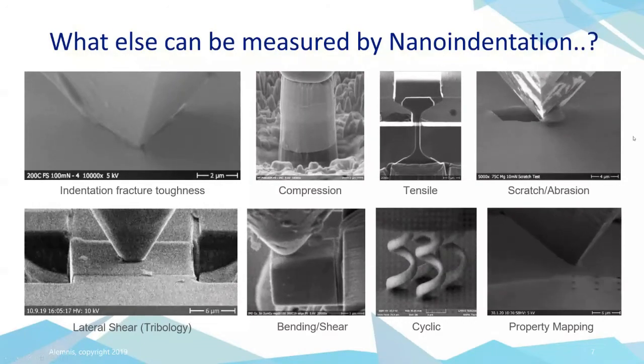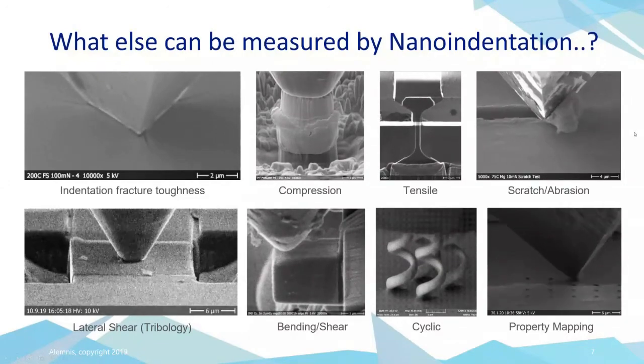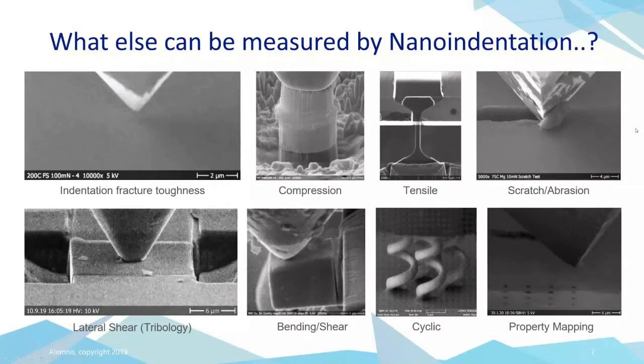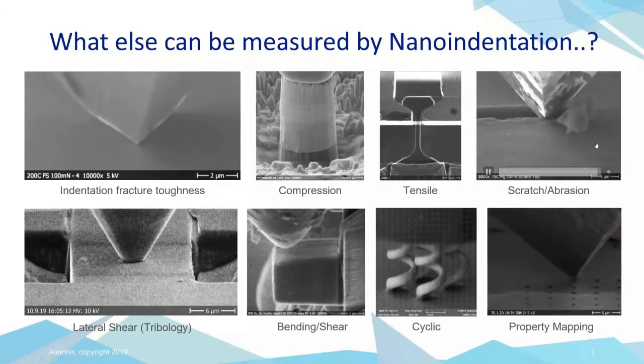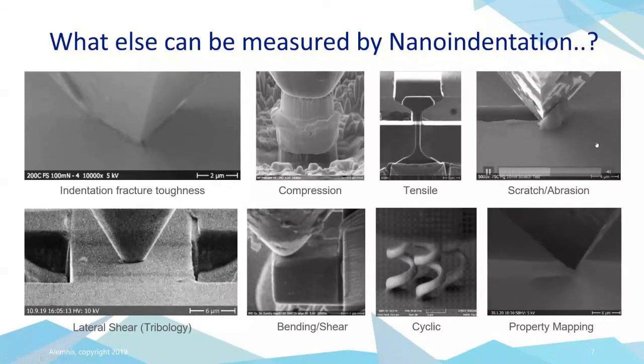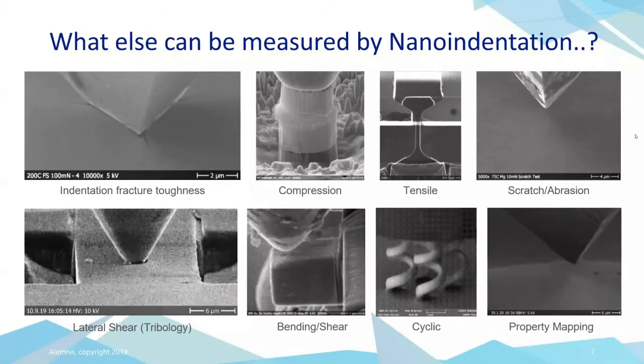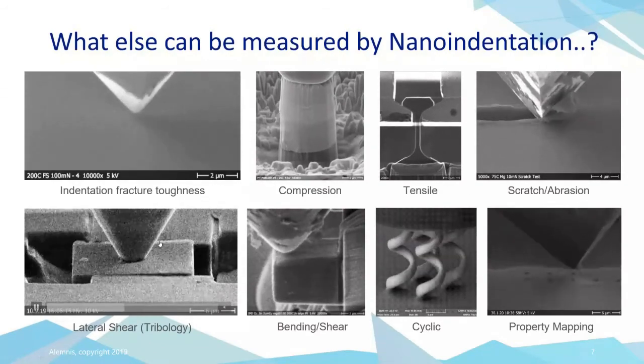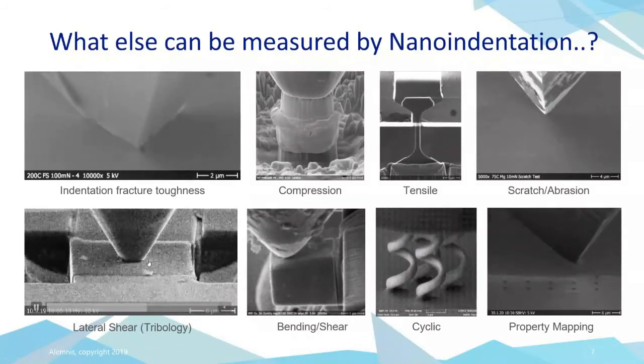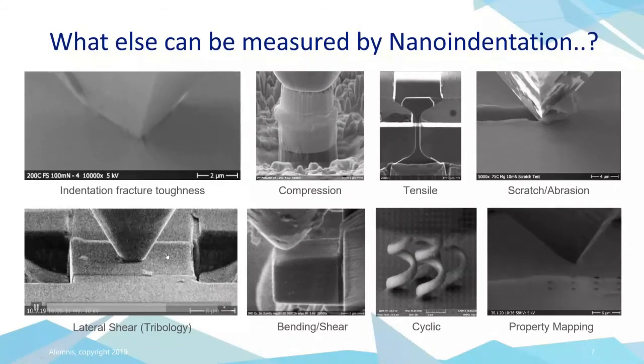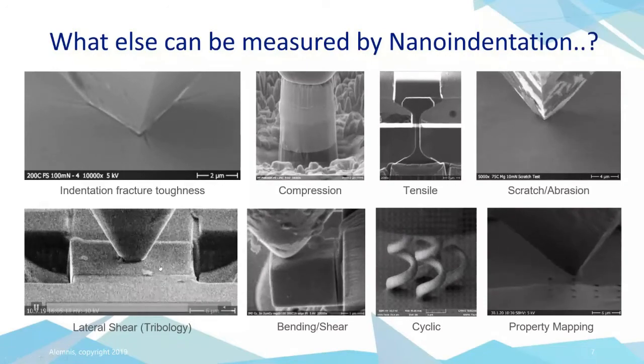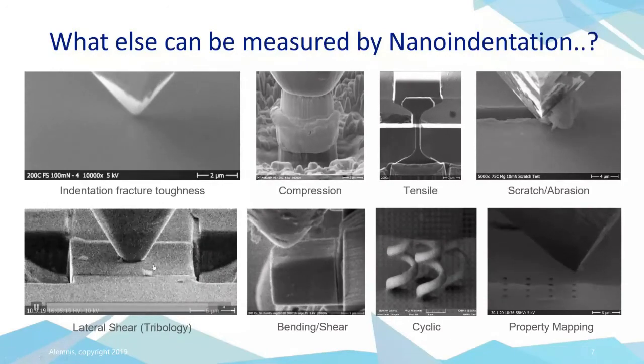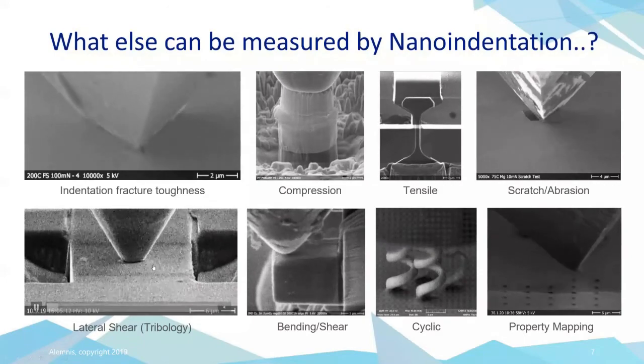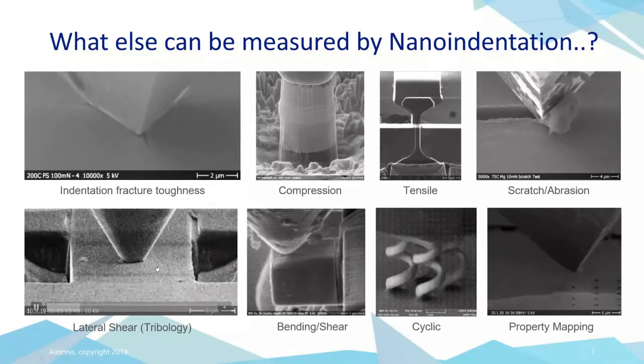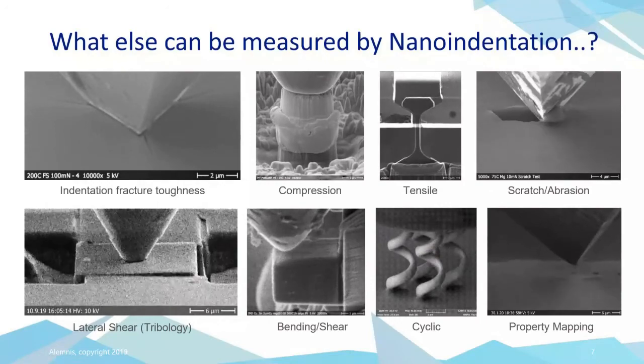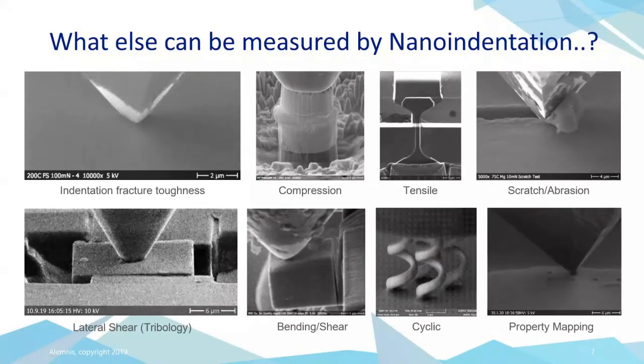We have a lateral force sensor to be able to do scratch testing. So scratch and abrasion of the surface, and also investigating how material recovers after scratching, which is very important in aesthetic applications. Down here on the bottom left, we've got lateral shear. So this is a more specialized application where we're picking up a fiber in a composite matrix, and we're basically displacing it tangentially so we can break the fiber out of its matrix and therefore measure the interfacial shear strength. So this would be a typical tribology type test.